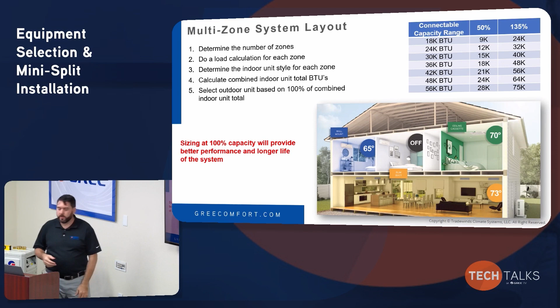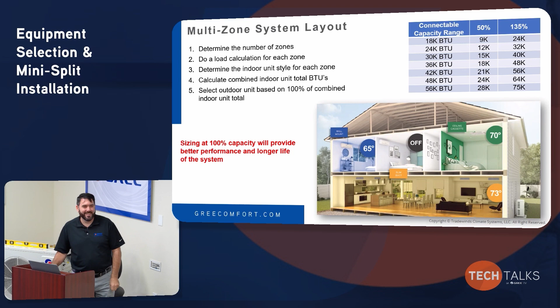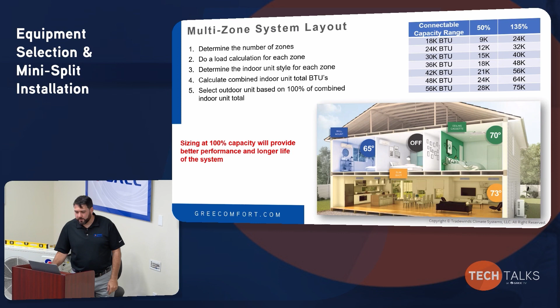Well, the other thing you got to think about here too is the golden rule of zoning: just because you can zone every room doesn't mean you should zone every room. Very true. It may be more beneficial to combine a couple rooms into one zone. And that's the good part about Gree's multi-zone units, is you have a variety of indoor units you can use. You don't have to use a wall mount in every room. You could use a ducted unit and pick up 2 rooms.